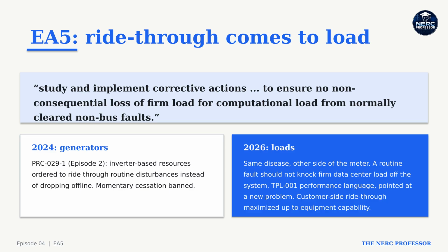Sound familiar? It should. In episode 2, we walked through PRC 29-1, where regulators forced inverter-based generation to stop dropping off the grid during routine disturbances. Same disease, other side of the meter. Generators that quit during faults got a ride-through standard. Loads that quit during faults are next. Everyone still reads ride-through as a generator topic. This alert says otherwise.